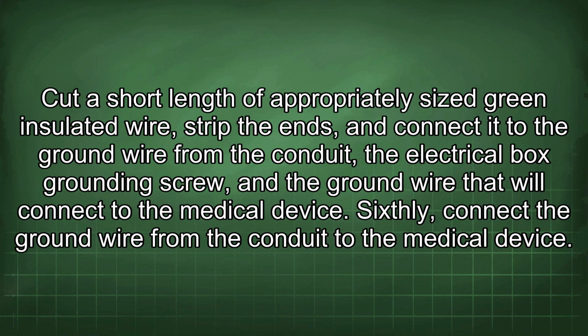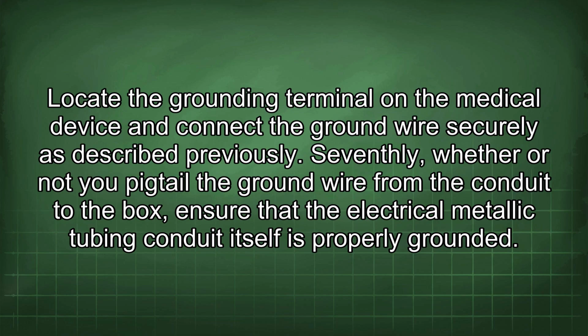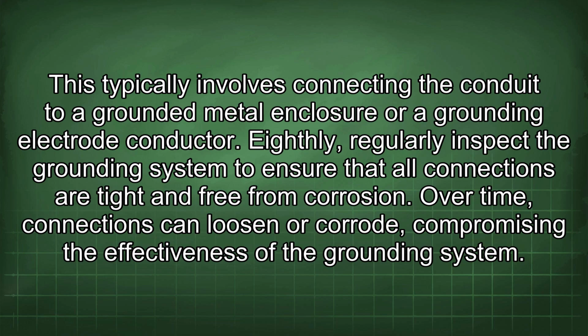Sixthly, connect the ground wire from the conduit to the medical device. Locate the grounding terminal on the medical device and connect the ground wire securely as described previously. Seventhly, whether or not you pigtail the ground wire from the conduit to the box, ensure that the electrical metallic tubing conduit itself is properly grounded. This typically involves connecting the conduit to a grounded metal enclosure or a grounding electrode conductor.